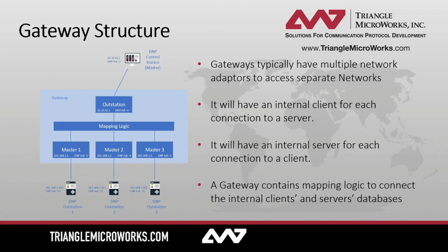So how exactly does this happen? Well, gateways typically have multiple network adapters so they can access multiple different networks. For each of the connections to an outstation or server, you'll need to have an internal server database or internal master database. And then for each control station or master connection, you'll need to have an internal database as well, like an outstation or server. After that, you can use the mapping logic here in the middle to map the points that you're interested in from the masters to the database. Once that happens, your database will be filled with the information from the external devices and available for your control station.